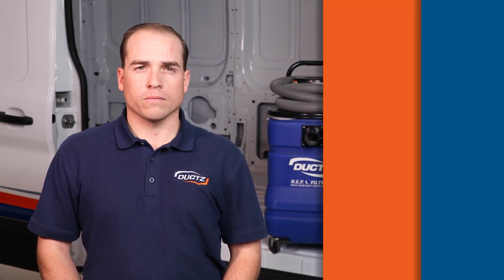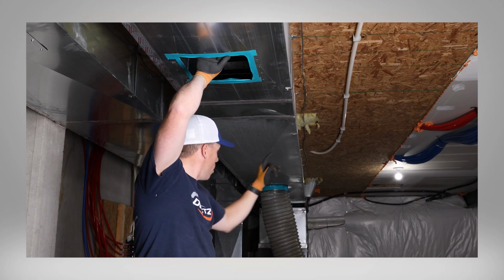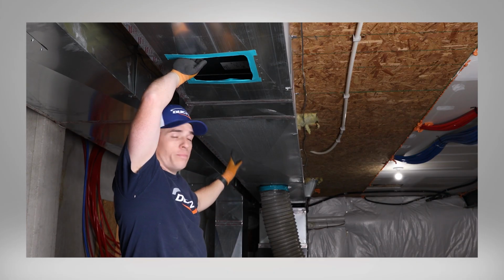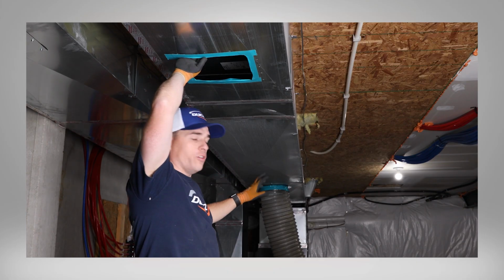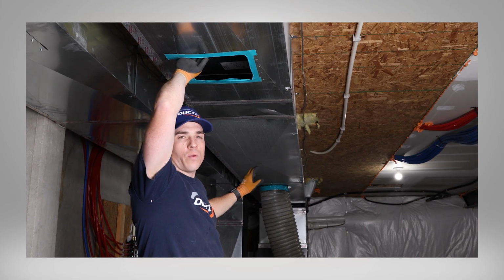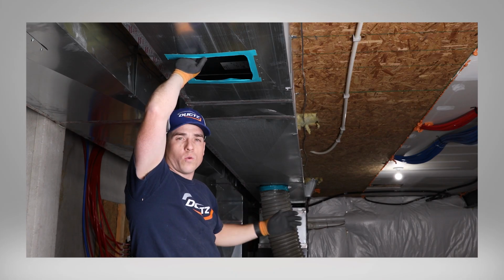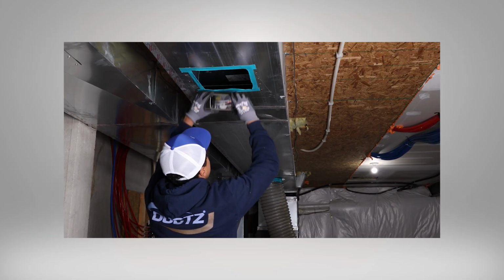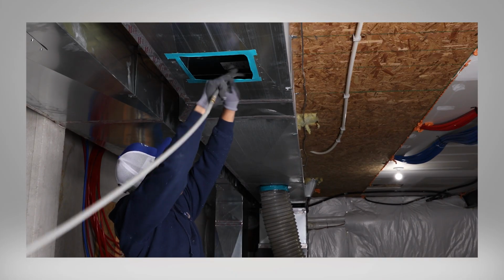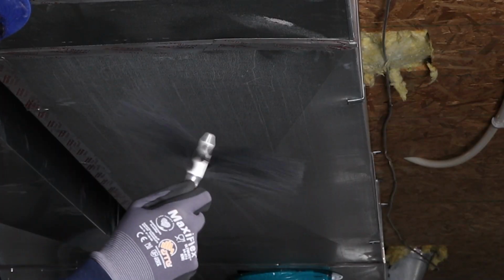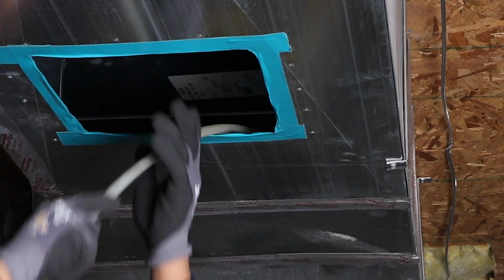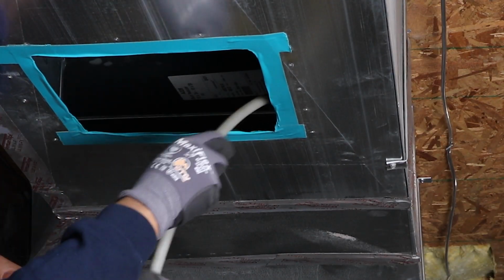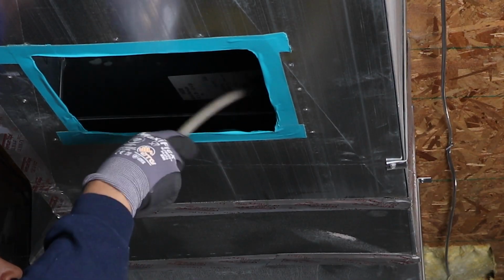Just like with cleaning the branch lines, we repeat the same process for the trunk lines. As you can see back here, we have the negative air hooked up to the supply trunk. The unit is completely disassembled so we could get in there and clean it, take the blower wheel outside, power wash it, and now we're going to begin cleaning the supply trunk lines, pushing all the dirt and dust back to the negative air so it can suck it up and run it through the HEPA filters.